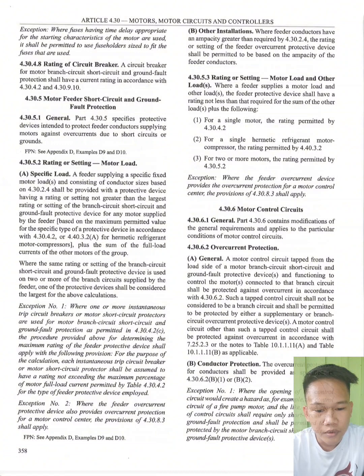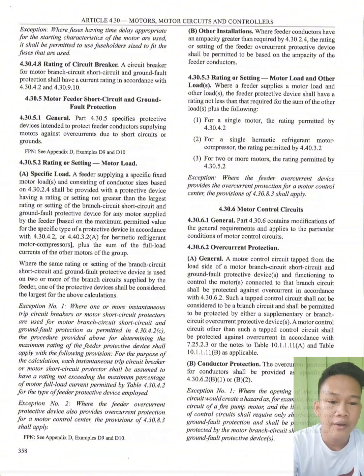B. Other installations. Where feeder conductors have an ampacity greater than required by 4.30.2.4, the rating or setting of the feeder overcurrent protective device shall be permitted to be based on the ampacity of the feeder conductors. Next is 4.30.5.3, rating or setting, motor load and other loads.